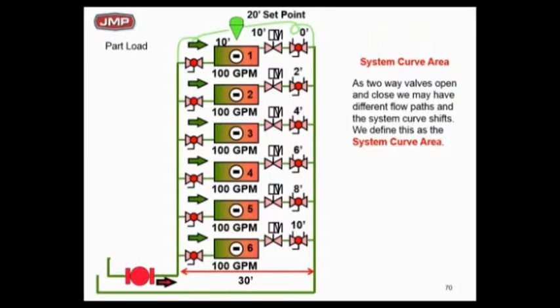Now, if everything's wide open, all the two-way valves are wide open at 600 GPM, one percent of the time, we know where we are. But anything less than that, do you know what your system curve is doing? Do you know really where you are? I'll give you an example.